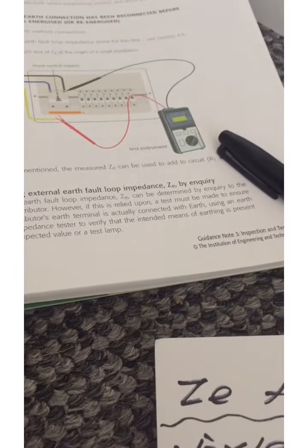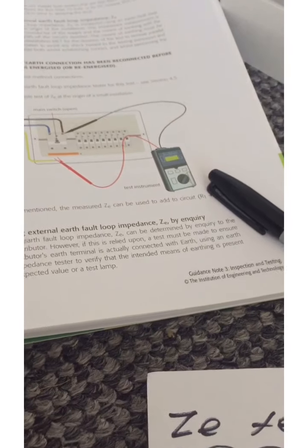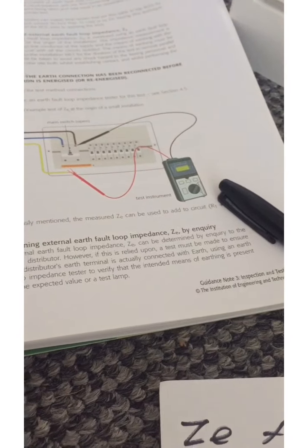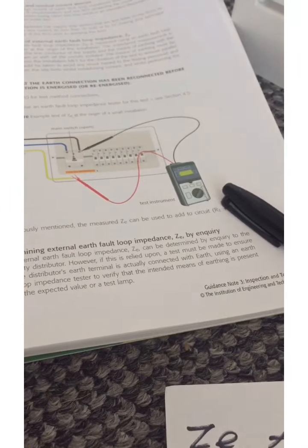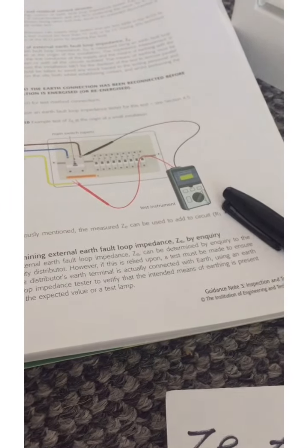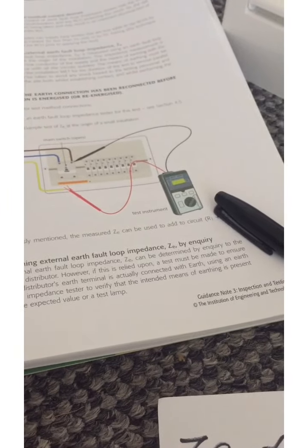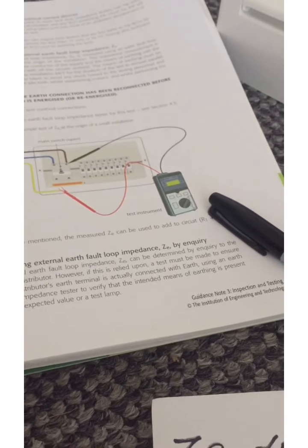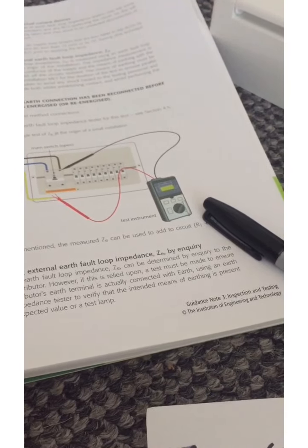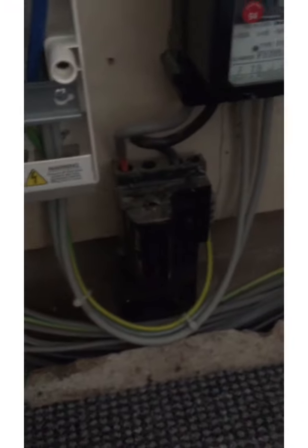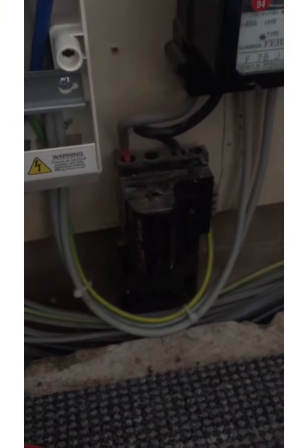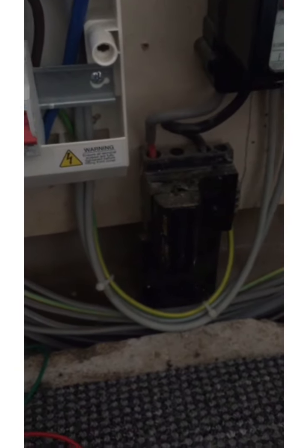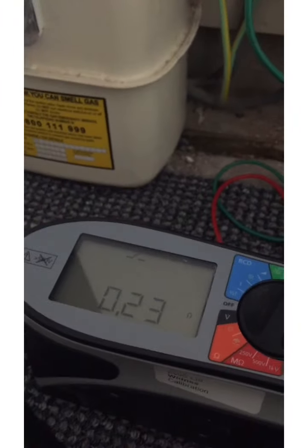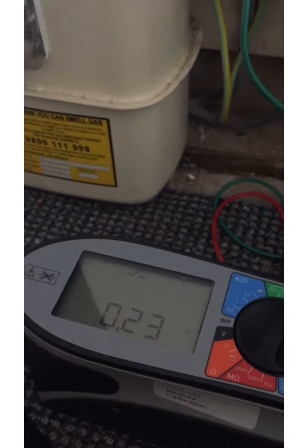Let's have a look what it says there. It's telling us there, however, if this is relied upon, a test must be made to ensure that the distributor's earth terminal is actually connected with earth, using an earth fault loop impedance test to verify that the intended means of earthing is present and of the expected value. So there we go. So we expect it to be 0.35 or thereabouts, and we're getting 0.25. So normally in this situation, we're going to measure the value. It's going to give us obviously greater accuracy.